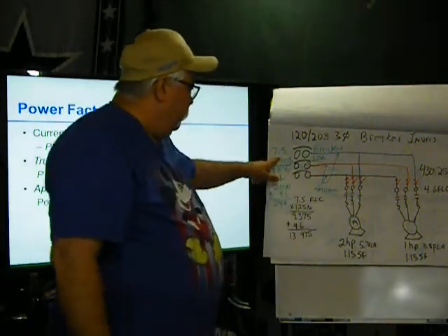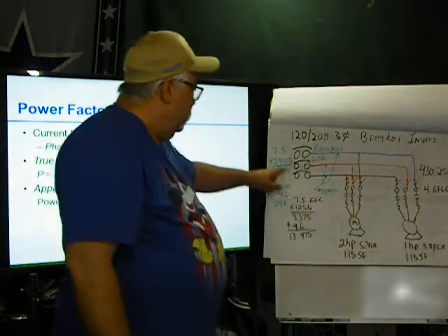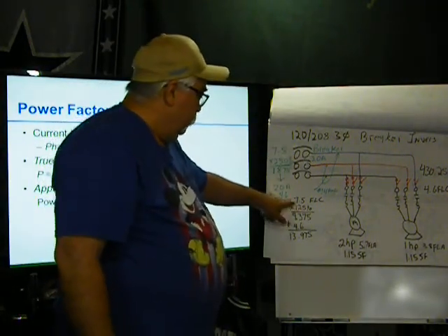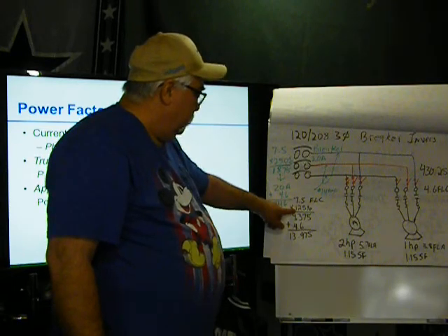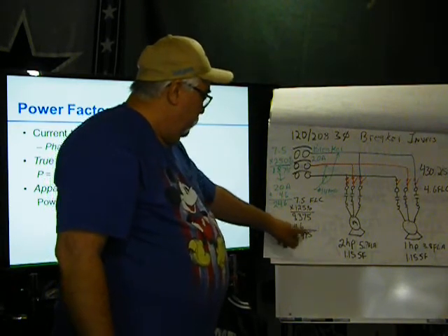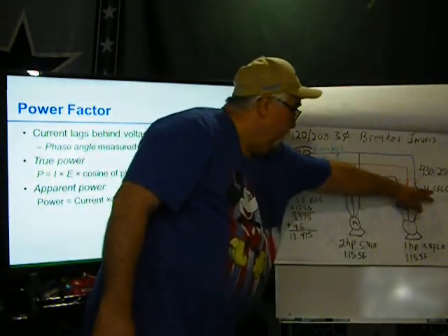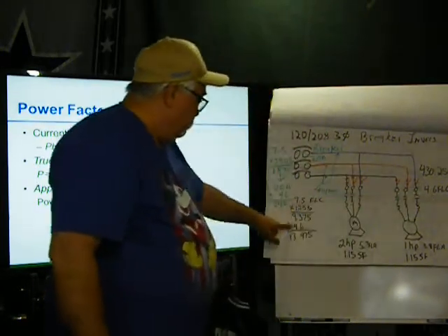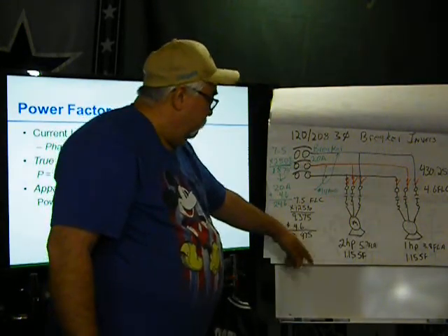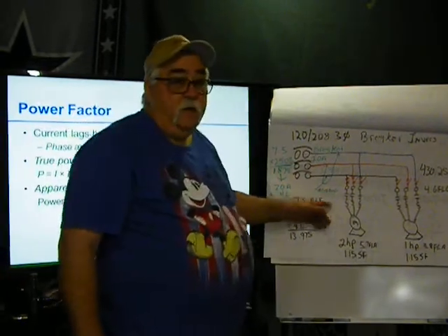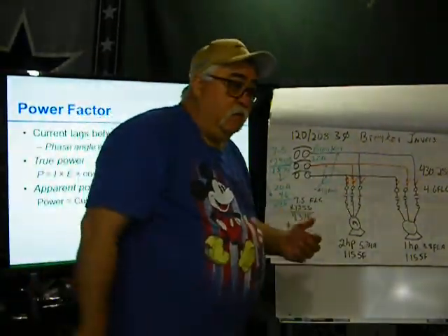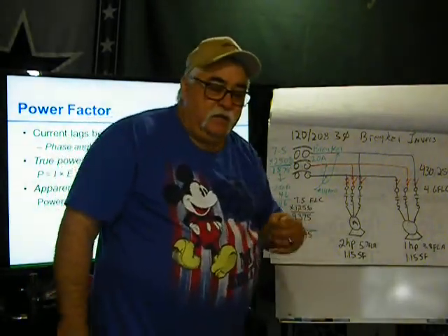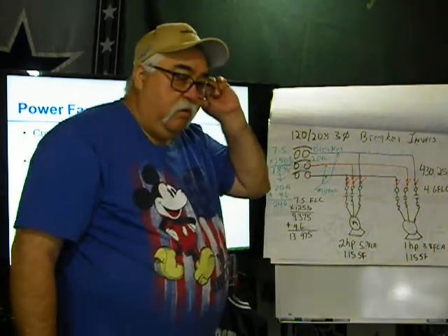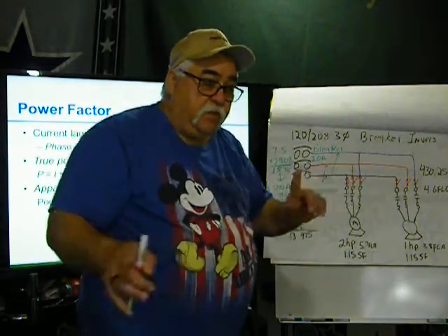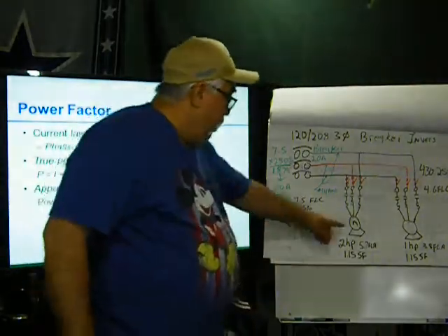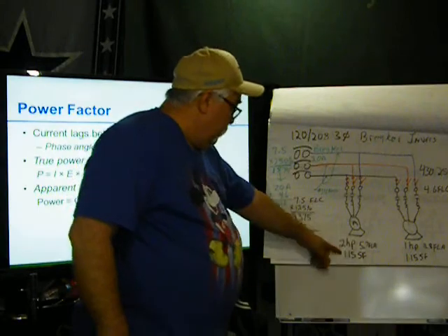For my wire, again, use my largest motor, which is a 2 horsepower, 7.5, right here. 7.5 times 125% gives me 9.375. Add the other motor, which is this one here, 4.6, not down here but over here, and that's 13.975, 14 amps, that's a 14 gauge wire. When we're wiring motors, the smallest building wire is 14. You can use smaller wires if you're doing your protection and everything else. If I had it from here to here, I could use a 16 gauge.